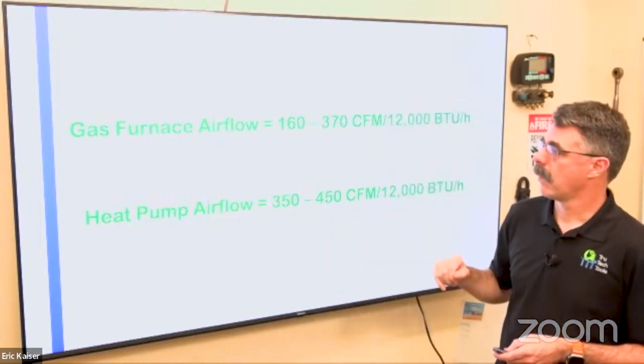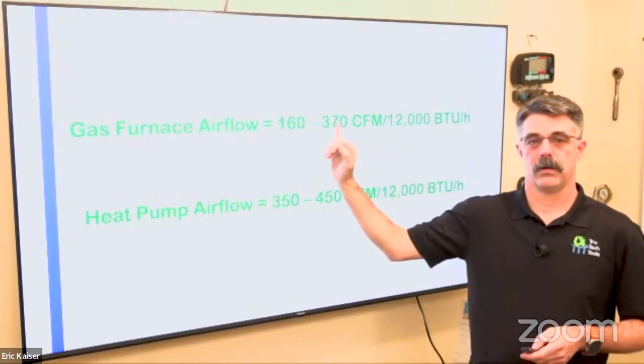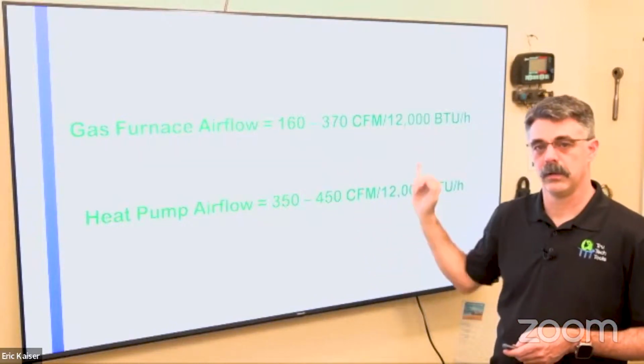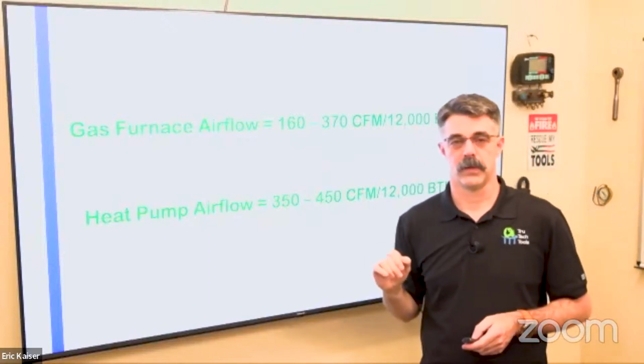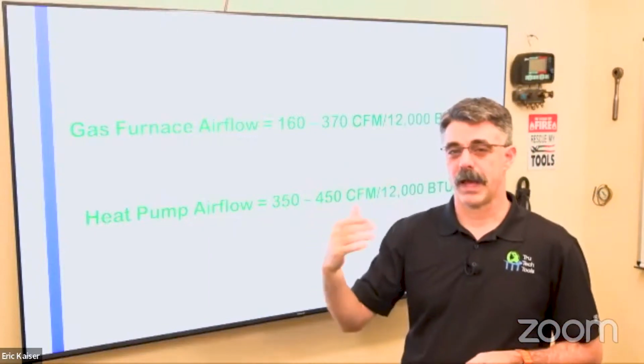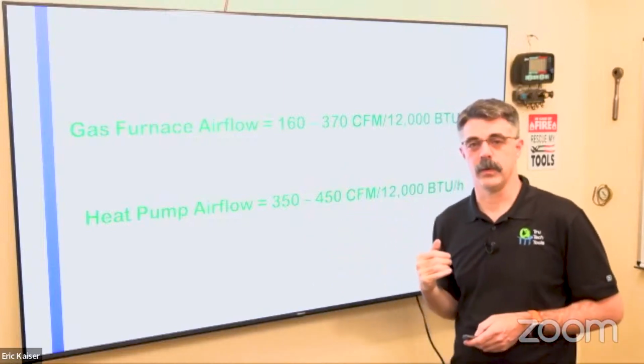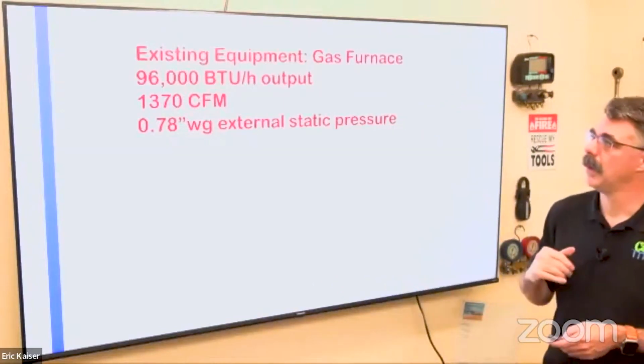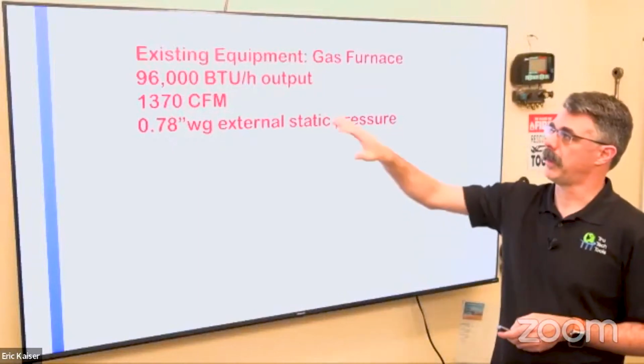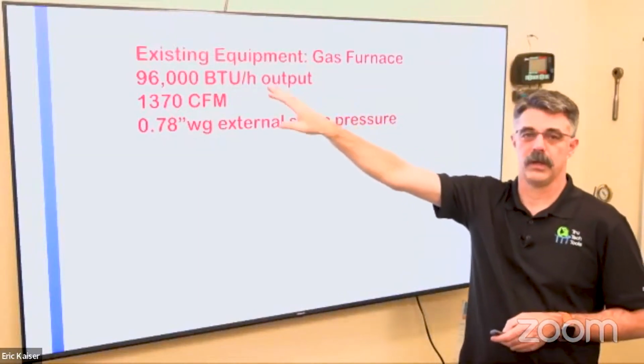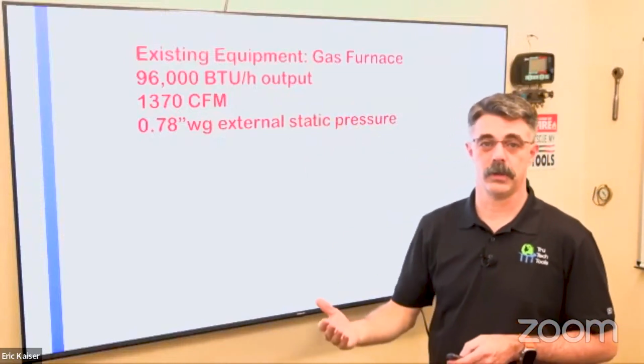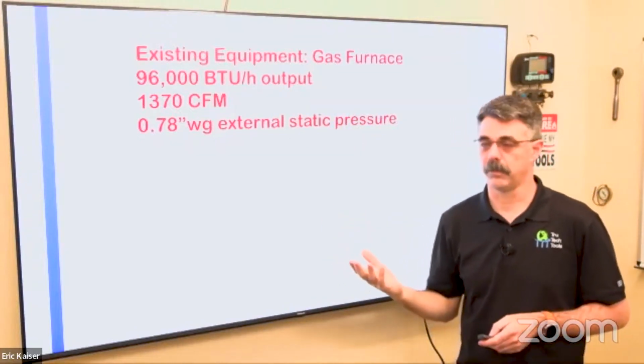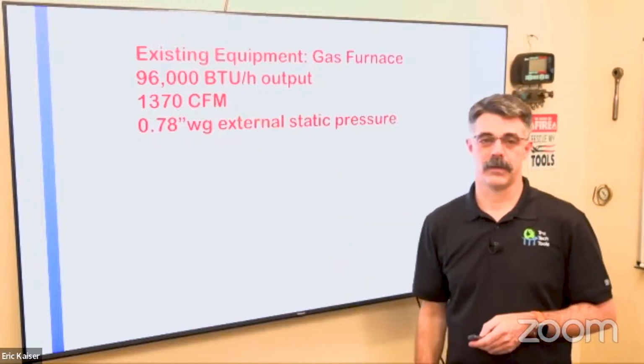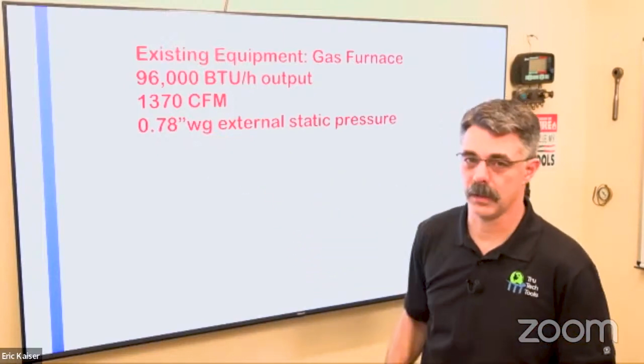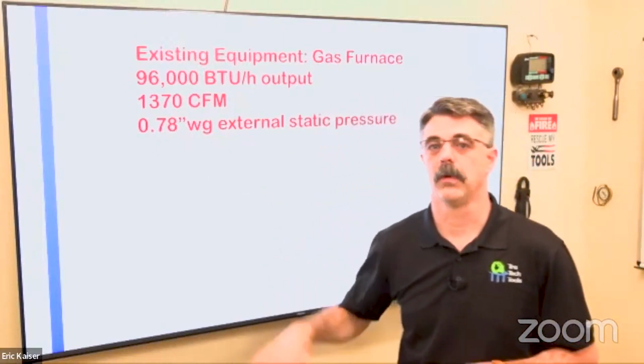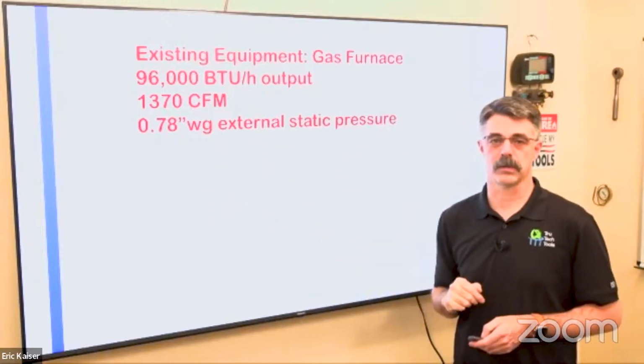Now, remember we have our airflow here. We may have different BTU numbers, right? These are just per 12,000. But remember those static pressure and airflow readings that we took before. Okay, here's an example. We're going to talk about existing equipment. We've got a gas furnace, 96,000 BTUs per hour of output. Okay, so that would be a 100,000 nominal furnace, right? 1,370 CFM. Existing 0.78 inches of water column, or water gauge, is our external static pressure.